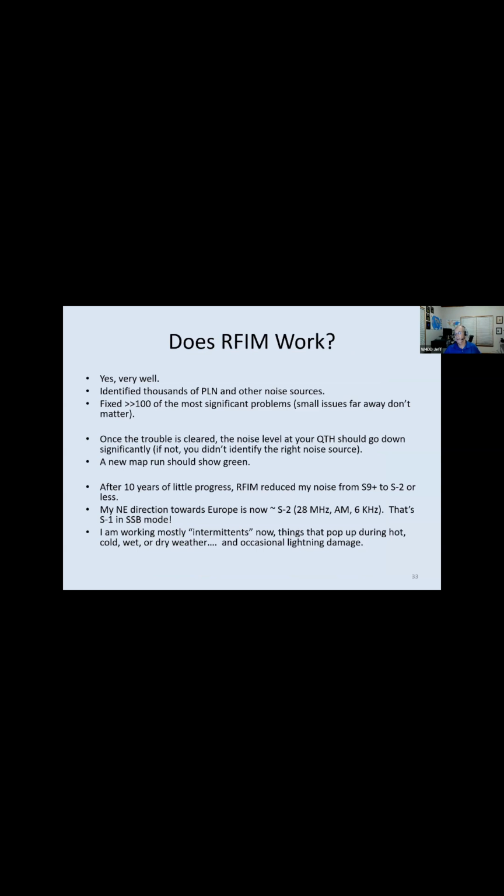I can send them a map of what's going on, and they can look at that and go, yeah, this is a map. I mean, it's not personal opinion. There's a receiver looking at the noise floor, and sure enough, this area seems to indicate it. They used the Yagi to find the pole, and they used the dish to ID the part on the pole. So I try and narrow it down right down to the part, so there's no doubt about it: yeah, we've done our homework and here's what's going on.